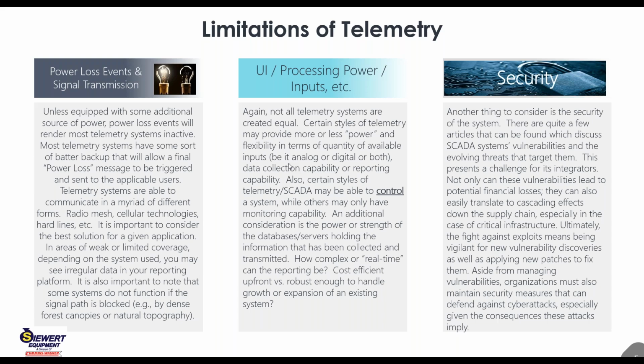In one version of telemetry, we have 5 analogs and 2 digital inputs. Each cellular modem can handle 7 different events: an alarm event, an alert event, a high level event, a power loss event, cellular inactivity. We just burned 5 out of the 7 with what I just said. The other 2 could be rainfall or humidity. There are other pieces of equipment that can handle many more inputs, be it analog or digital.